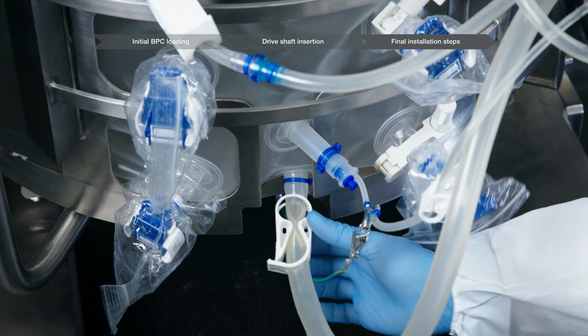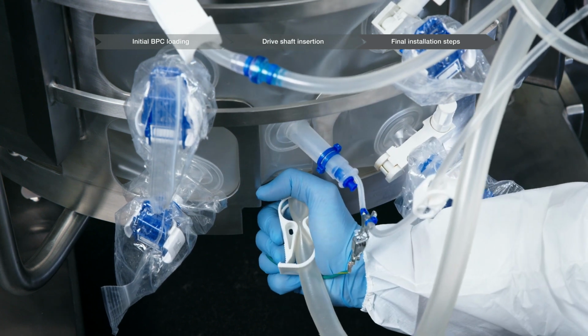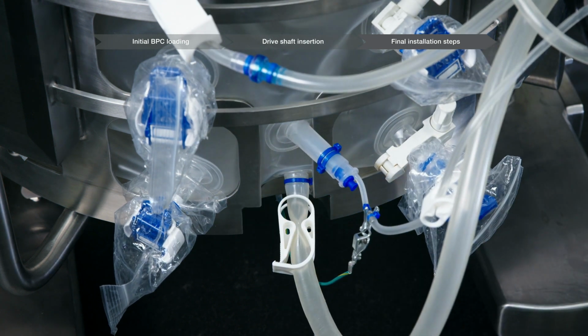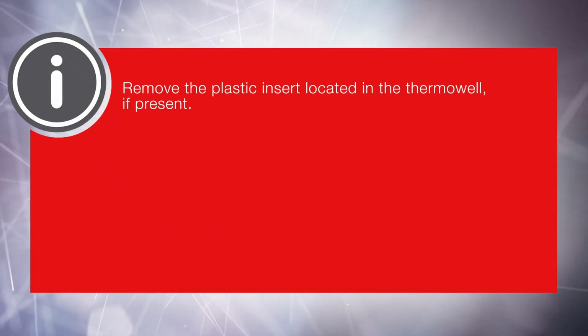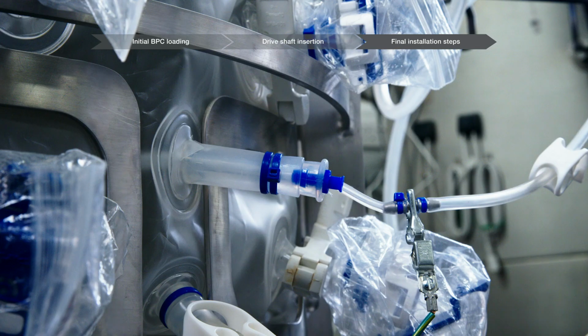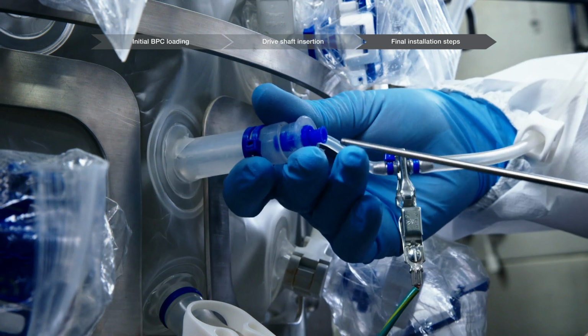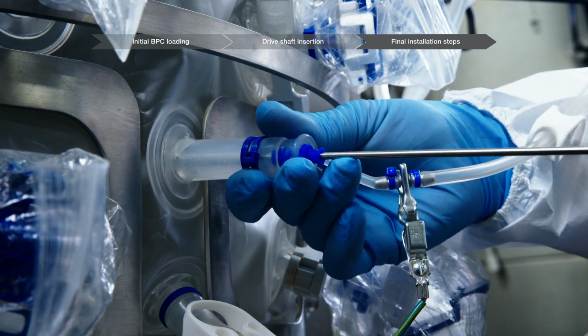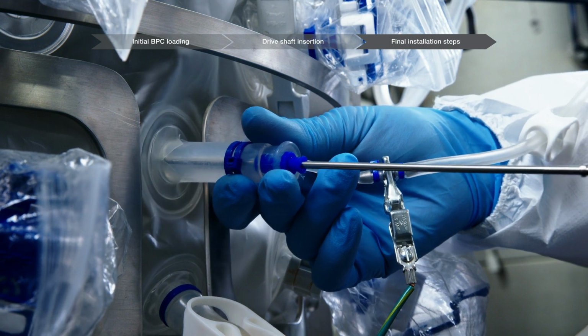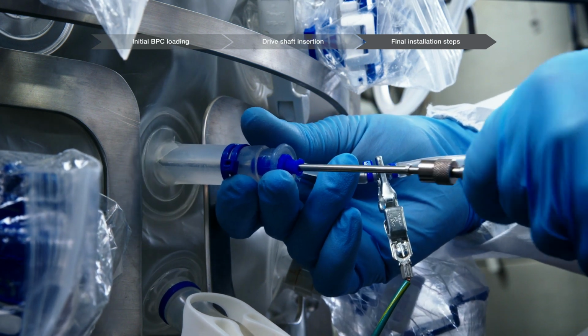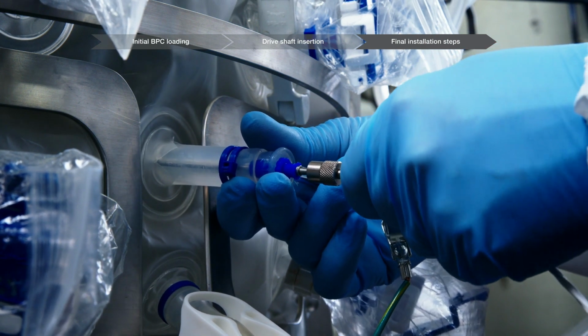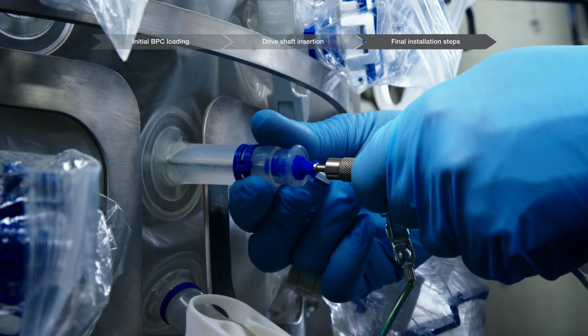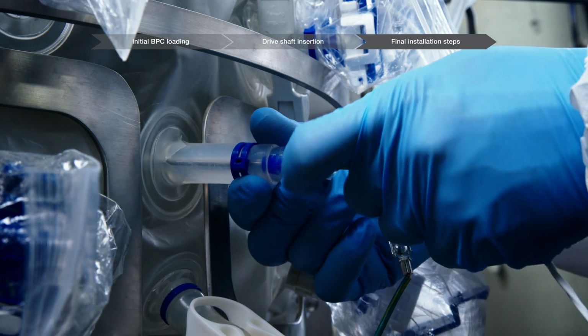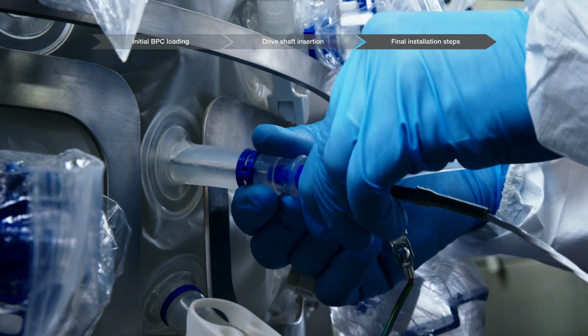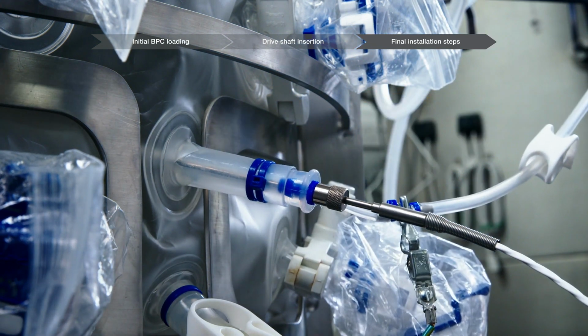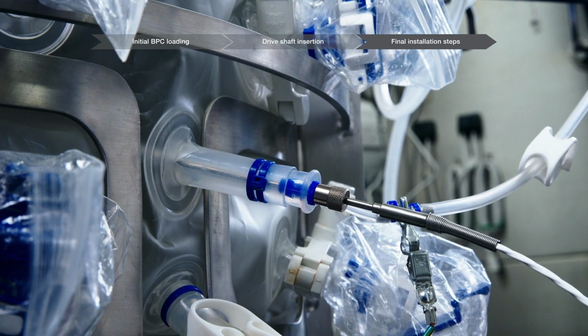Check to ensure that a bar clamp is closed on the bottom drain line as close as possible to the BPC port. Remove the plastic insert located in the thermo well if present. Insert the resistance temperature detector, RTD, or selected temperature sensor into the thermo well. Rotate the probe either clockwise or counterclockwise to aid insertion. The sensor should be inserted until the base of the probe meets the mouth of the thermo well. Secure by twisting the luer lock collar if provided. The thermo well will stretch slightly when the RTD is seated.